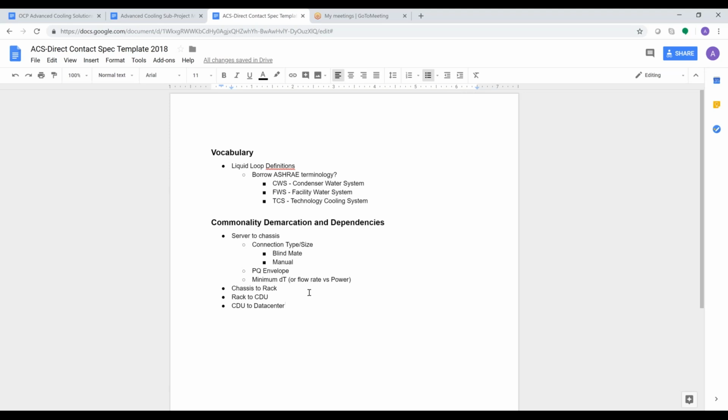I think that is going to be a different category because the liquid is non-conductive, and I think we have to be careful not to set our box too big. I think it's very important to have guidelines, if not specifications, geared towards the liquid and the wetted material list. And as soon as you go to another fluid that's not water-based, I think you're in trouble. So I would say, in the box, water-based cooling rather than the one that you just raised. It does get complicated.